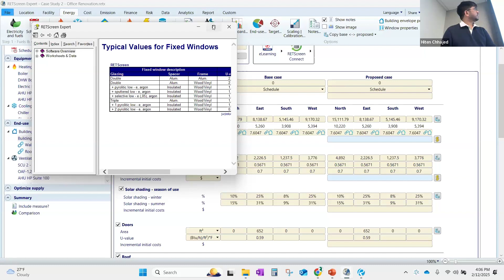Right now they are double pane, and what they're installing is the last row in this table, which is triple pane, low E argon plus 2, pyrolytic windows. I want you to use the total window value, not the center of glazing, the last column. So the first row is your base case, or what's currently in the building, and the last row is what the owner plans to replace it with. You can use those values and enter them in the proposed case.